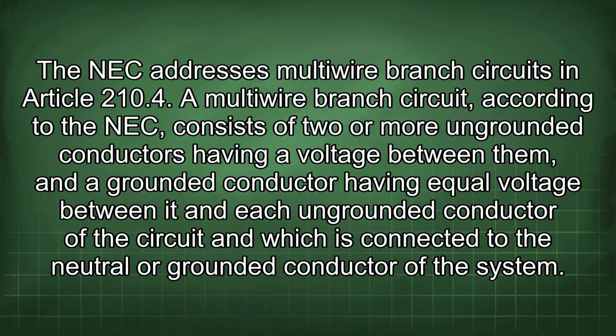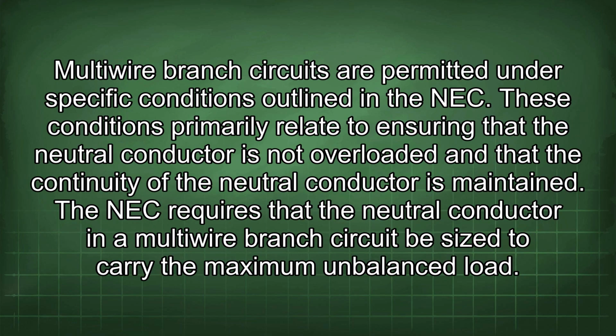The NEC addresses multi-wire branch circuits in Article 210.4. A multi-wire branch circuit, according to the NEC, consists of two or more ungrounded conductors having a voltage between them, and a grounded conductor having equal voltage between it and each ungrounded conductor of the circuit, and which is connected to the neutral or grounded conductor of the system. Multi-wire branch circuits are permitted under specific conditions outlined in the NEC.